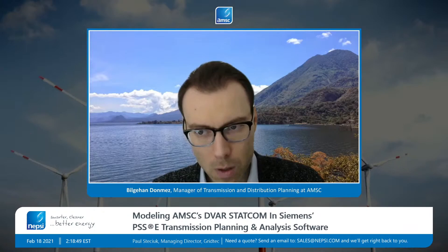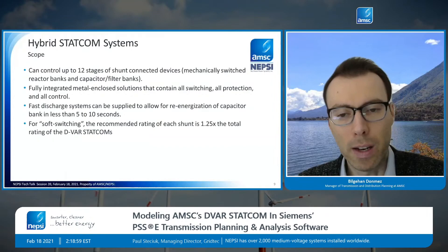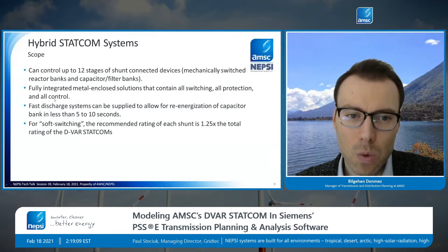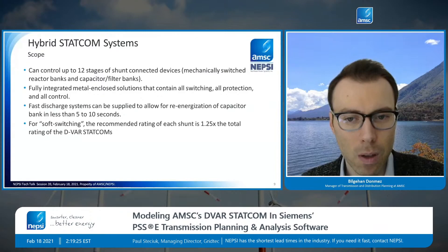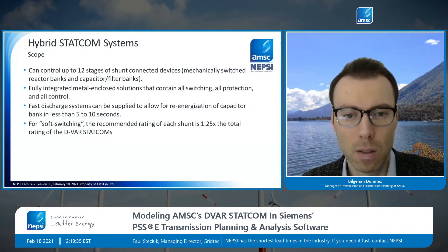There's a gray area in the definition of dynamic capability. When you switch in a capacitor and want to switch it back in, how quickly can you use capacitors for repeated applications? That's where fast discharge systems come into play. For re-energization of capacitor banks using fast discharge systems, it can be done in 5 to 10 seconds. Otherwise, without the fast discharge system, it can take a few minutes before you can re-utilize a capacitor.